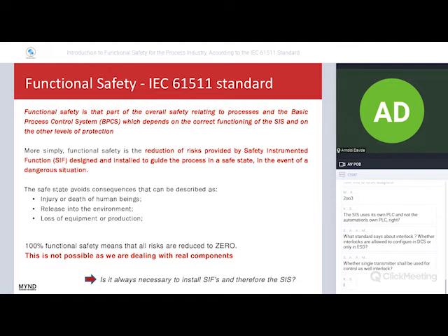Very well. Now we can define functional safety by the 61511 standard. The definition is: functional safety is the part of the overall safety related to the process and the BPCS, which depends on the correct functioning of the SIS and on the other layers of protection.